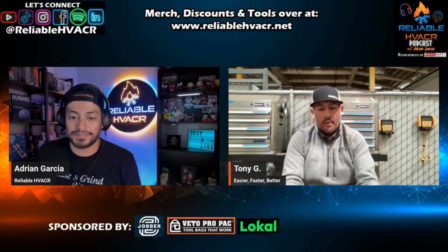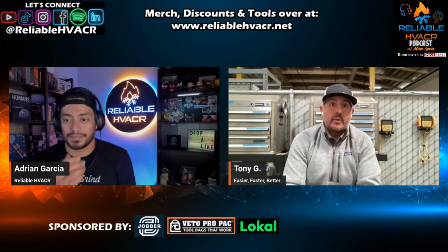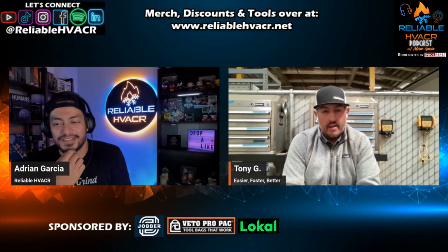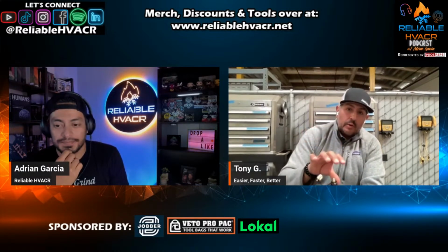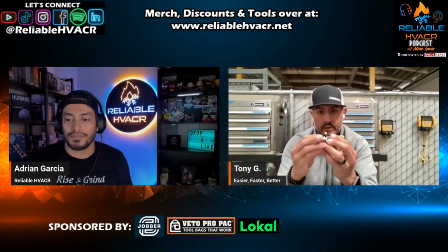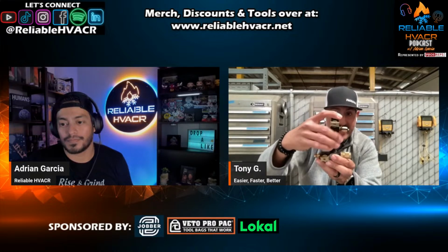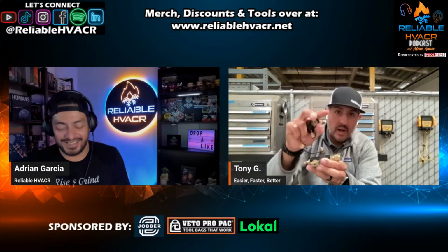Right. And so to that point of adding that extra connection, we have a system evacuation class, right? Where myself or my trainers teach how to pull a vacuum and what the best practices are. What is your procedure there? So specifically what we're talking about here with the VCRT is, on your traditional one, we would teach using either a ball valve like you said here, or maybe even a second valve core removal tool, and screw it on there. But the problem is two.